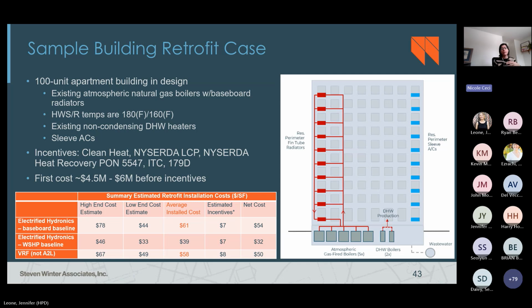And those are both expensive. That said, I see a lot of variability in this pricing. $45 to $60 per square foot is a lot of variability for one building, and a lot of that is driven by which air-to-water heat pump options we go with. In this particular example, the lower end estimate is a project where we pivoted to using the LG Hydro Kit as the basis of design for heating the entire building loop.